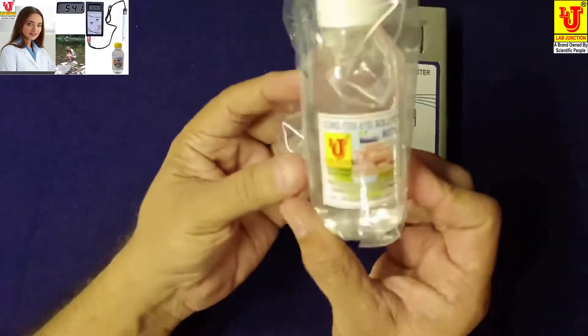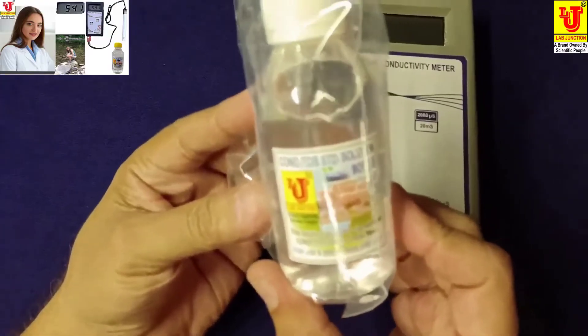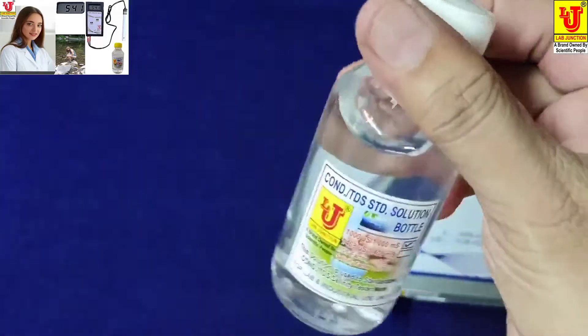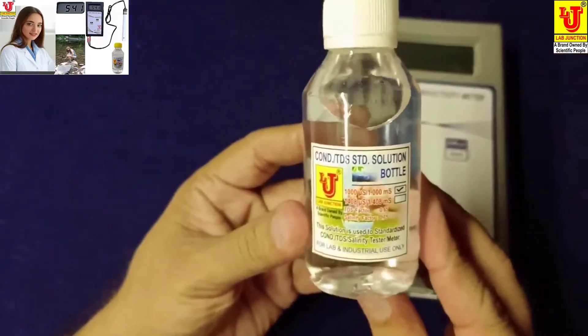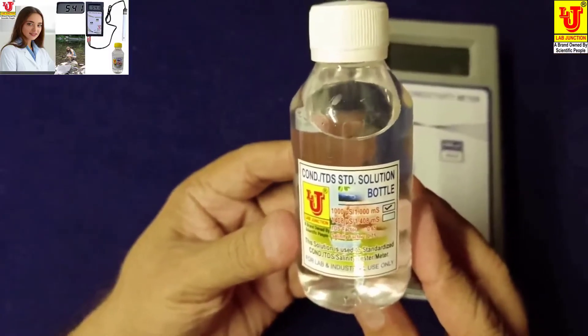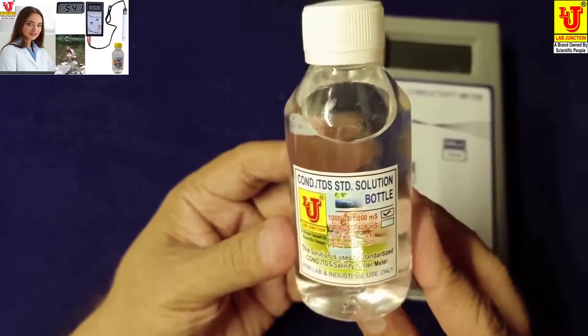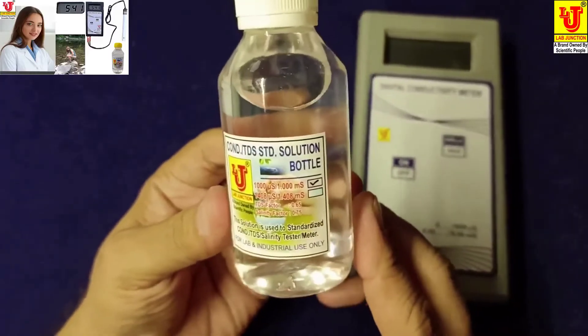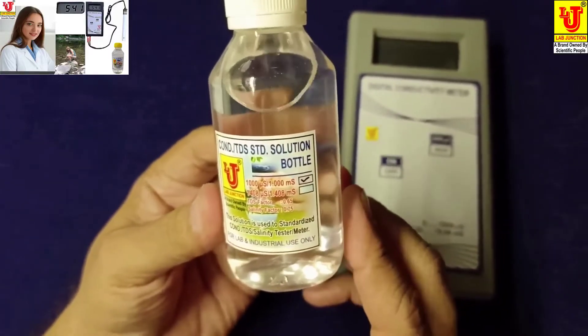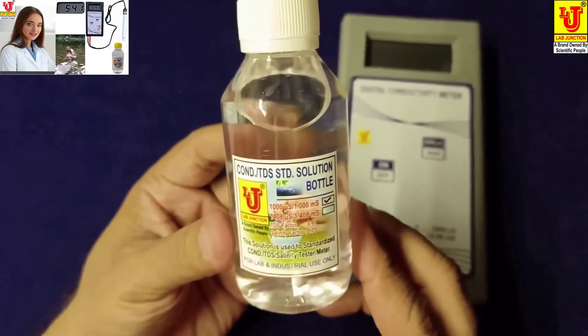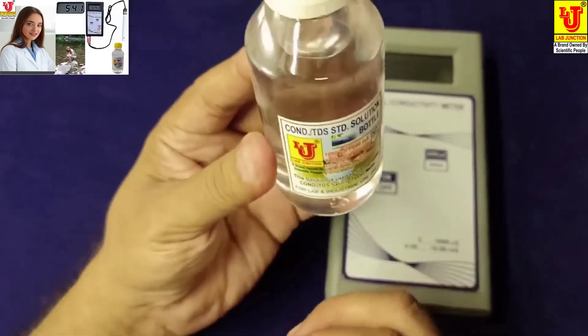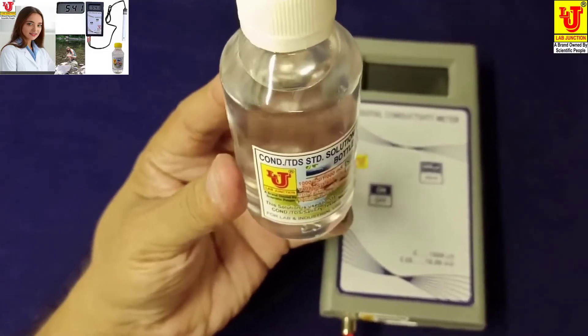One is conductivity TDS standard solution. Unpacking this. Value 1 millisiemens or 1000 microsiemens for calibration of portable digital conductivity meter. In this, net content 100 ml.